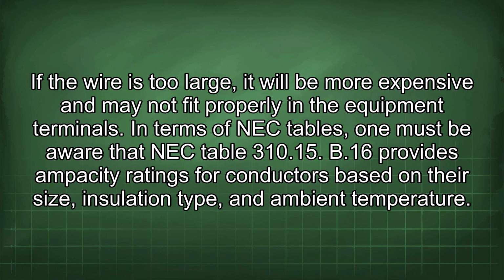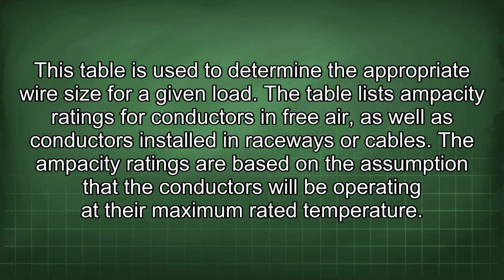In terms of NEC tables, one must be aware that NEC Table 310.15 B16 provides ampacity ratings for conductors based on their size, insulation type, and ambient temperature. This table is used to determine the appropriate wire size for a given load. The table lists ampacity ratings for conductors in free air, as well as conductors installed in raceways or cables.